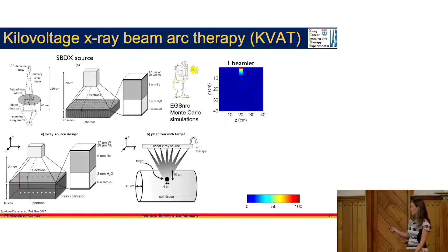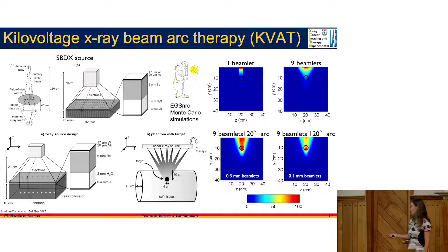When we look at a 120-degree arc, where this linear source moves in a 120-degree arc, you're finally getting at least the same dose in the target as you're getting on the skin, but of course this is still not very good. While you're treating the target, you're also treating the skin. But if you look at a different beamlet width, and basically redesign this collimator, you're now getting the most dose in the target and not as much dose on the skin. So this is sort of the idea.